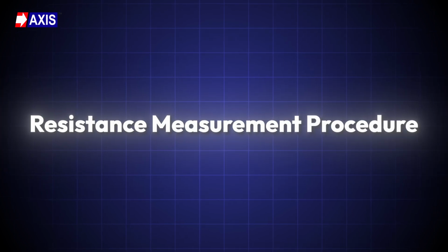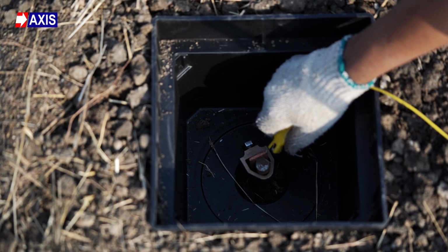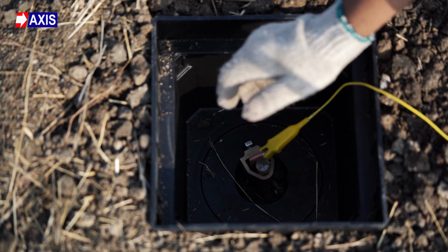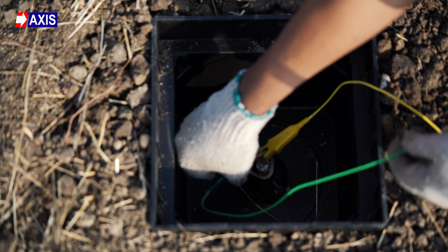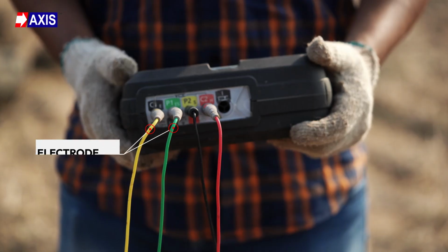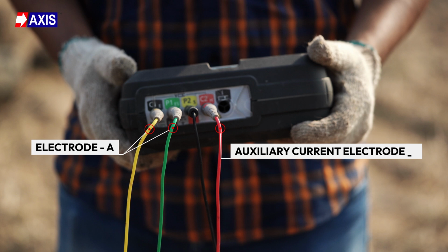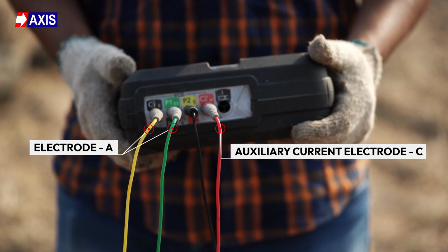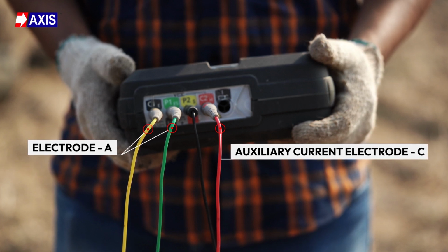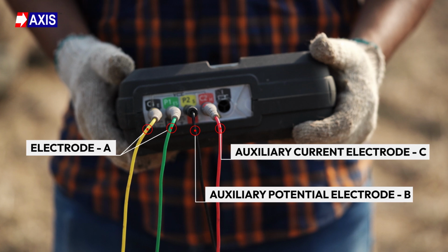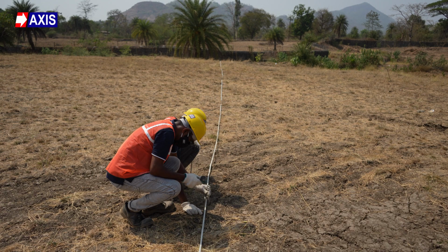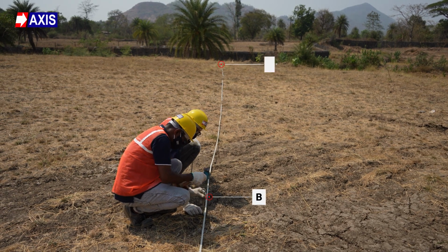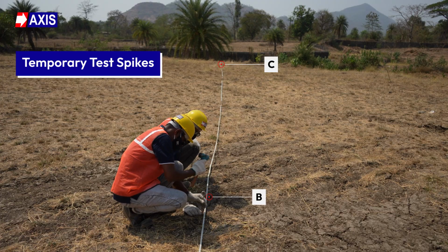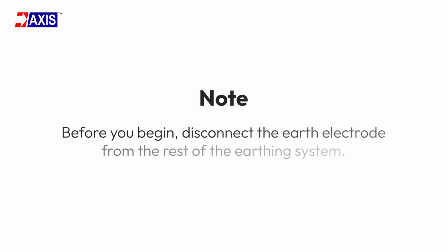Now, the measurement procedure. You will need 3 electrodes for this test. The first is the earth electrode you are testing. Call it electrode A. The second is an auxiliary current electrode. Call it C. The third is an auxiliary potential electrode. Call it B. Electrodes B and C are temporary test spikes. Note: before you begin, disconnect the earth electrode from the rest of the earthing system.